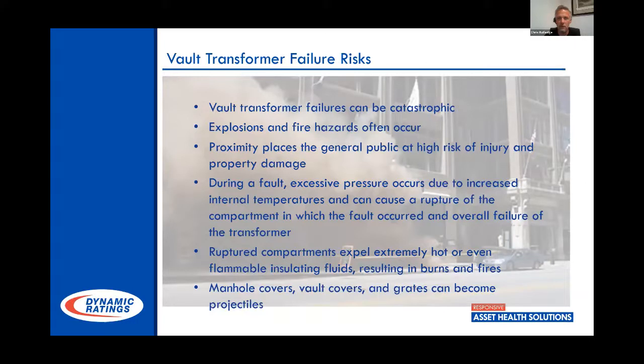So these smaller compartments are very susceptible to rupture, just because the internal pressure during any type of fault grows so quickly, and there's nowhere for expansion to happen. When they do rupture, in the cable compartments or switch compartments, there's almost always fire as a result of that. And then manhole covers, that kind of thing. I've seen vault grates blown completely out into the street, into cars, that kind of thing. So a lot of these covers can become projectiles during these events.